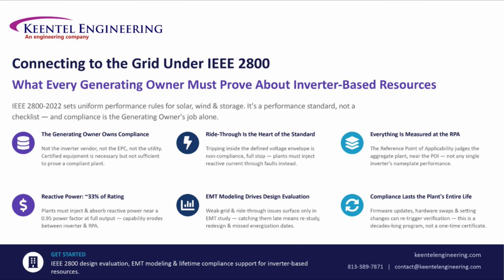Let's talk about what it actually takes to connect a solar, wind, or storage plant to the grid today, because the rules changed and a lot of developers haven't caught up. IEEE 2800-2022 exists because inverter-based resources behave nothing like the spinning generators the grid was built around. A coal or gas plant responds to a fault based on physics understood for a century. Inverters respond based on software. And when thousands of them react identically to the same disturbance, that's a system-wide risk, not a local one. The standard sets uniform performance rules to fix that.